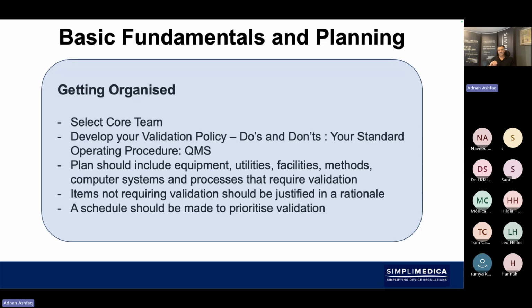And then you may also have some areas where validation will not be performed, and you need to be prepared to have a robust justification or rationale to make sure that you have adequate backing for not performing the validation. And it may not be so simple as because you're doing 100% verification. Now, there are times where you have some processes which have a bit of a black art involved, and there can be quite a bit of science in the control of validating the systems.